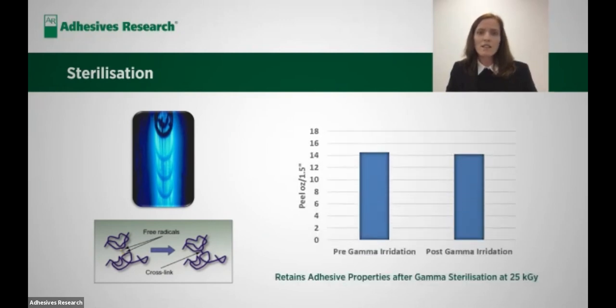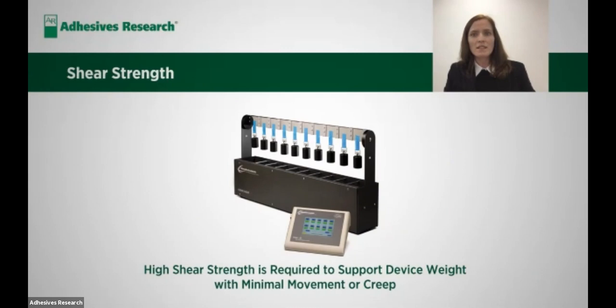Here we see illustrated in this graph an example of how the adhesive maintained its peel adhesion post-exposure to gamma sterilization at a dose of 25 kilograys. The shear strength of an adhesive is the maximum shear stress in the adhesive prior to failure under torsional load. High shear strength is required to support device weight with minimal movement or creep.